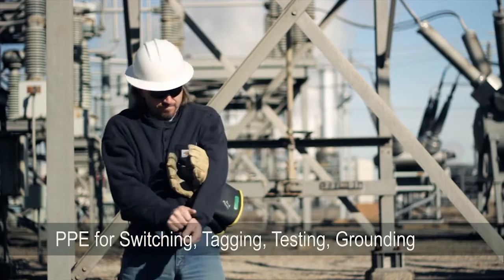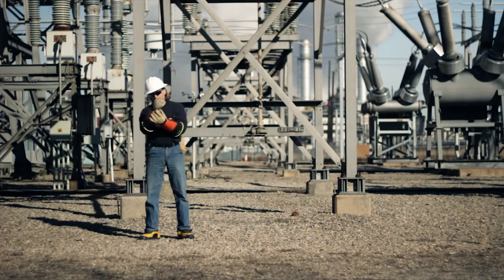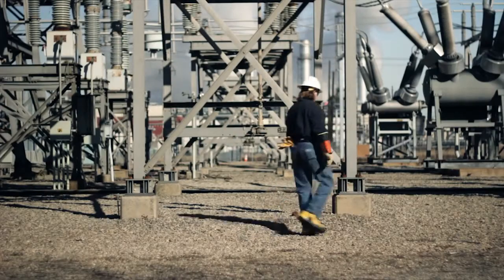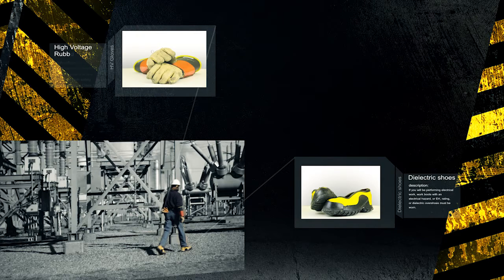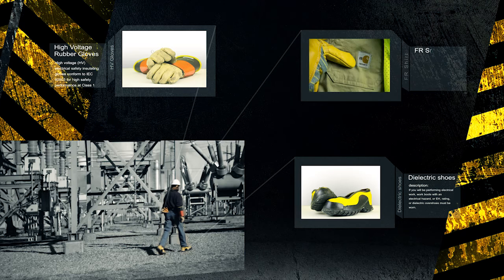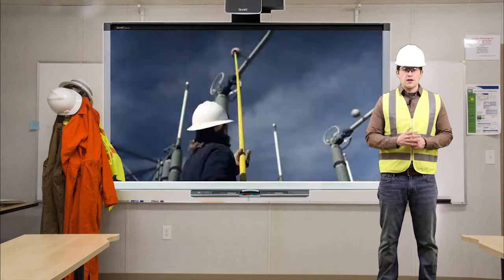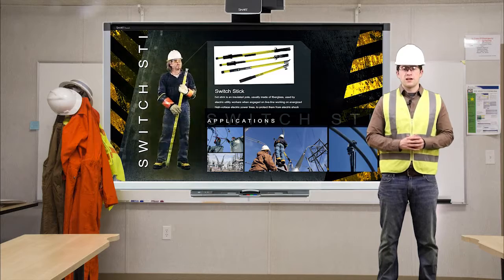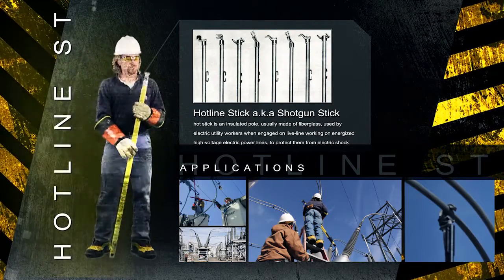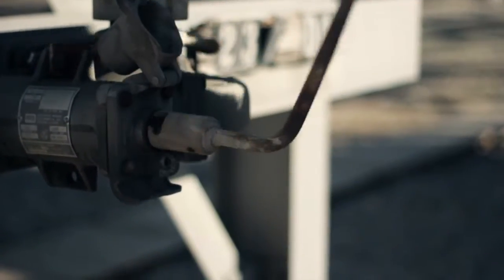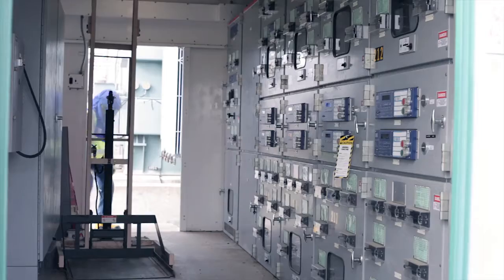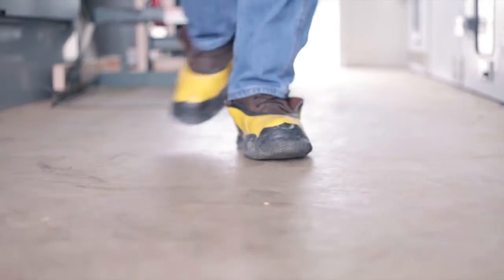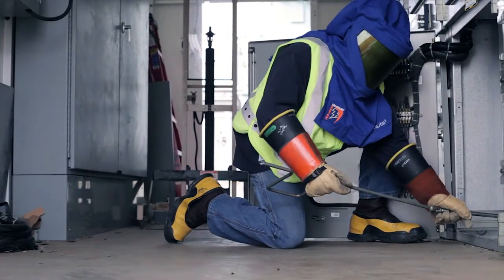Wear the applicable PPE prior to operating any switches, pulling fuses, testing for de-energized, and grounding of lines and equipment on the PHI high voltage electric system. This includes electrical hazard rated or dielectric footwear, high voltage rubber gloves for operating switches, cutting or disconnecting ground wires, and flame resistant clothing. Additional equipment consists of approved switch stick for opening single pole disconnect switches, fuses, and applying tags using an approved tagging device, approved voltage detector, used for testing for de-energized lines, and approved insulated hotline stick, also known as a shotgun, for applying protective grounds. Wear all PPE properly while performing switching, tagging, testing for de-energized, and grounding. When switching circuits or equipment rated 250 volts and above, if a 6-foot minimum distance cannot be maintained from the face or head, arc flash goggles or face shield and the appropriate flame-resistant hood shall be worn.